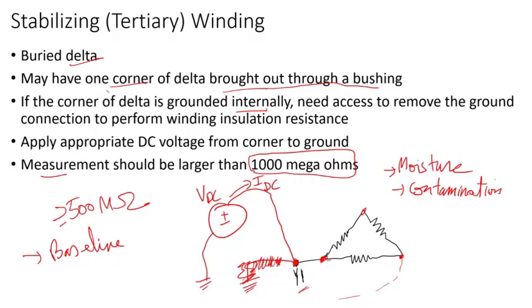Unfortunately, this stabilizing delta sometimes has one corner grounded internally. You cannot apply this test unless you remove that connection from the delta corner to the ground. If it's grounded internally you have to access that inside the tank. It depends - if it's brought up towards the tank cover, you probably have to remove the cover depending on the size of the transformer.